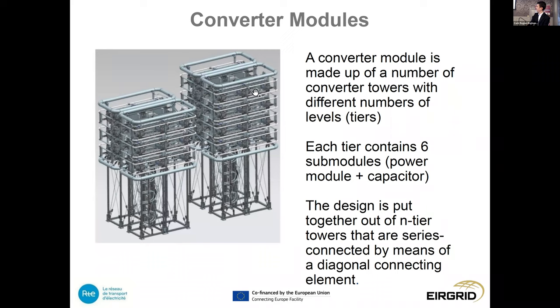The amount of tiers and sub-modules depends on the application, the level of redundancy required, and the maintenance interval. It's a flexible, modular solution that can be expanded to various power capacity levels, though the control algorithms involved are of significant complexity. For the Irish converter station, this is a plan view of the tender proposal. The DC cables come in on one side, through DC reactors into the converter arms — the modules, tiers, sub-modules, power modules, and capacitors all contained within these blocks.